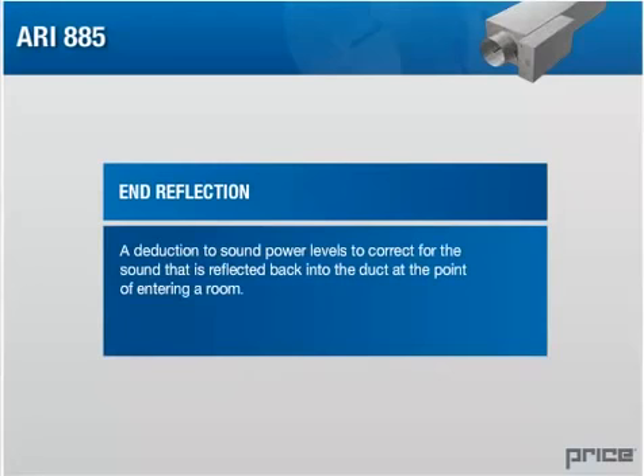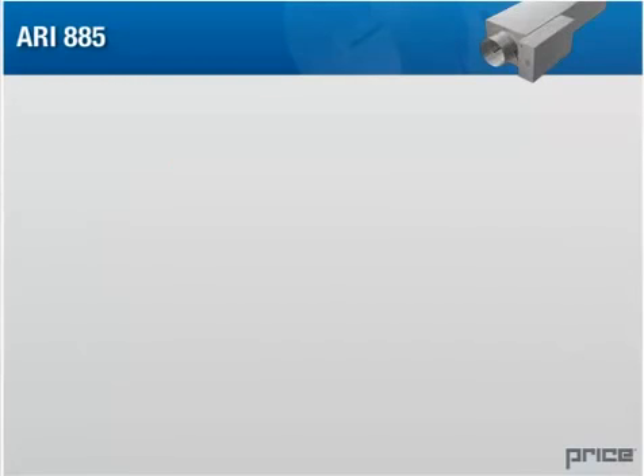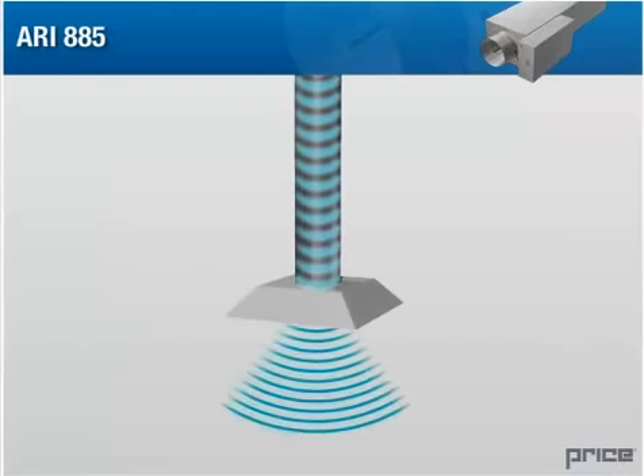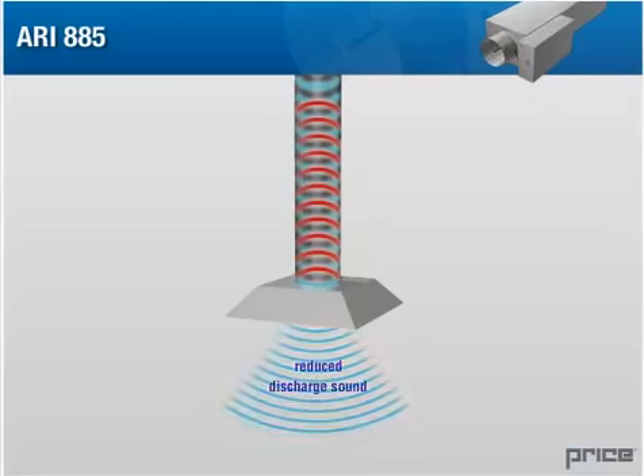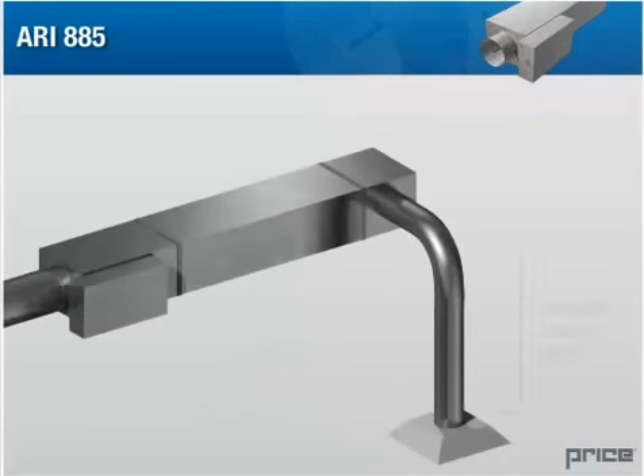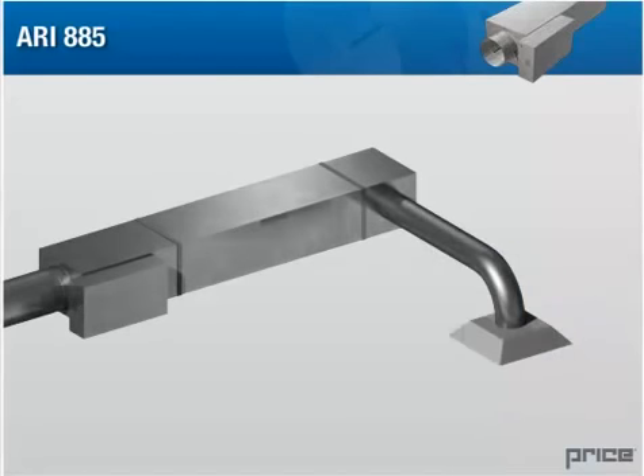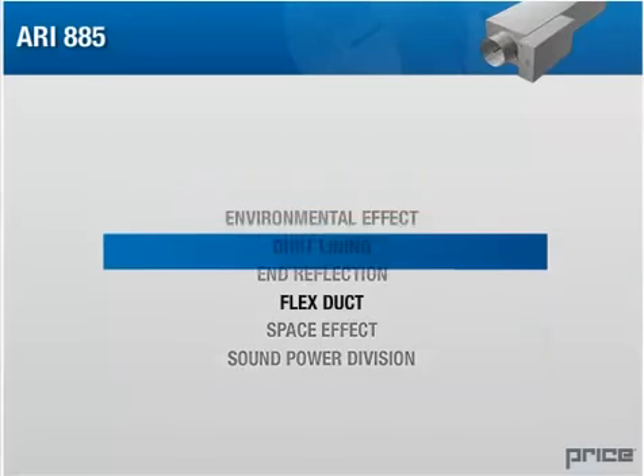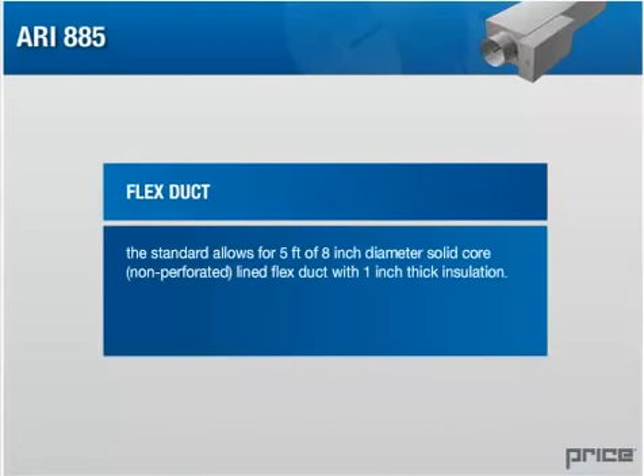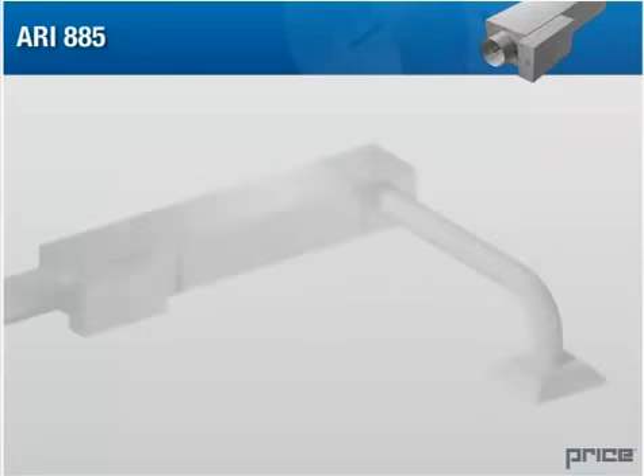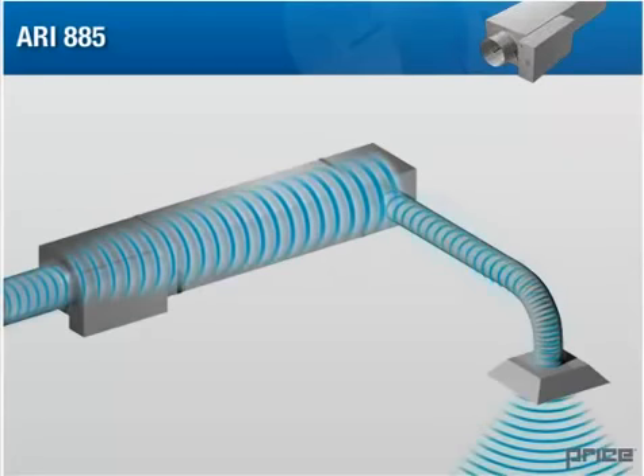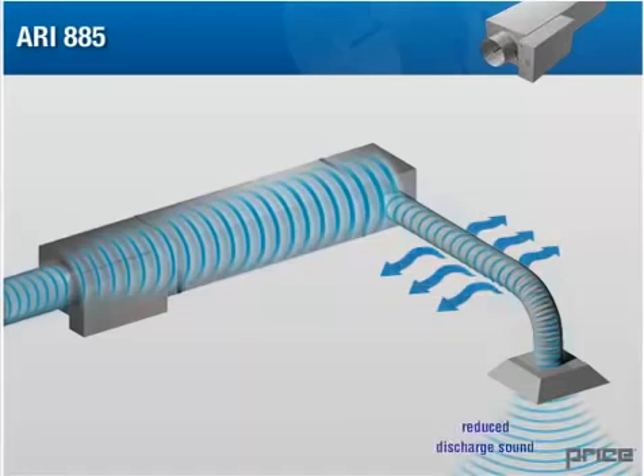End reflection. A deduction to sound power levels to correct for the sound that is reflected back into the duct at the point of entering a room. When low-frequency sound waves pass from a small space such as a duct into a large space the size of a room, a certain amount of sound is reflected back into the duct, significantly reducing low-frequency discharge sound. Please note that this assumes a straight run of duct to the outlet. Caution should be taken when conditions are drastically different. Flex duct. The standard allows for 5 feet of 8-inch diameter solid core non-perforated lined flex duct with 1-inch thick insulation. As sound passes through the flex duct, some is absorbed and some transfers through the wall of the duct. Deductions are made to account for this reduction in discharge sound.